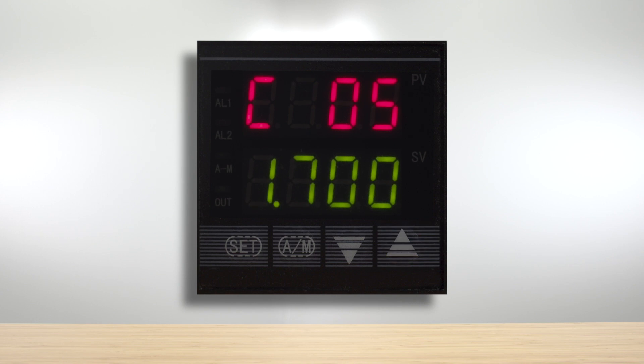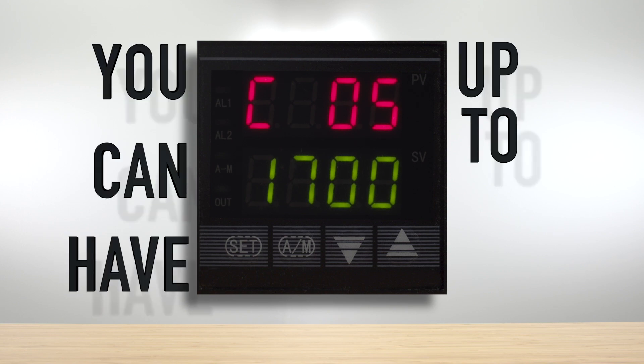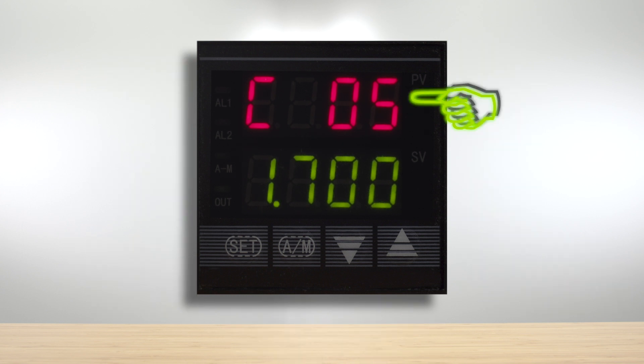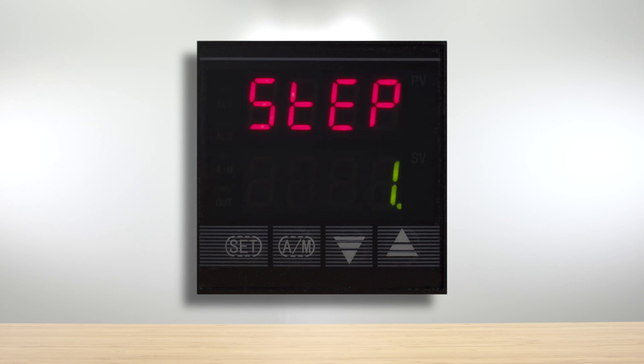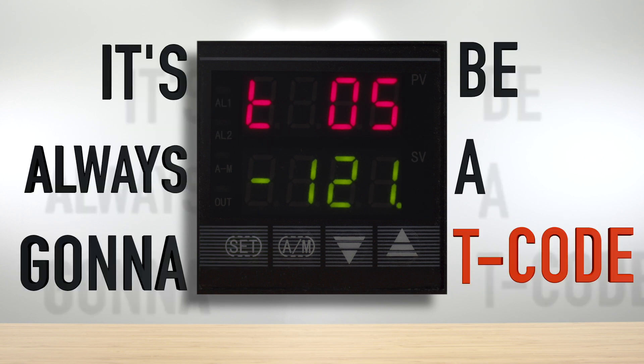Now that we've set our final temperature we want to tell the unit that we're at the end of a program. You can have up to 30 steps preset into this controller and obviously we're only at step 5 at this point. A single C and a single T code make up one step together. If we left the furnace like this and we started that burn off it's going to run through step 5 and it's going to want to go on to step 6. So what we can do to stop that from happening is there's an embedded code that we can put in the program of negative 121. That's always going to be at a time. So it's always going to be a T code. You can set it to negative 121 and basically that will tell the furnace when it gets to that step, that's the end of the program.